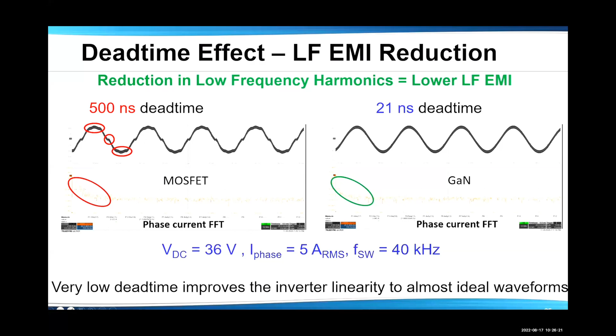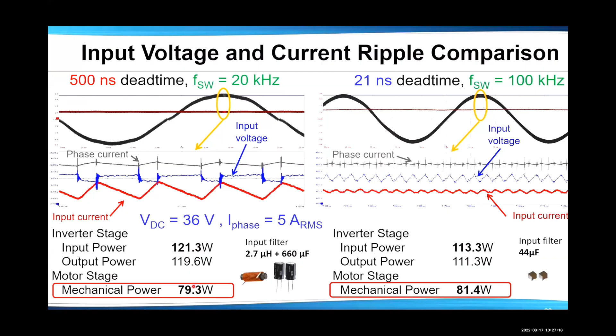Another really important thing is if you start going to higher frequency. This is an example from 20 kilohertz, 500 nanosecond dead time, same conditions, same motor. This is the input current from the battery. This is the input current at 100 kilohertz. This is the input voltage from the battery. This is the input voltage at 100 kilohertz. And here is the phase current. So all of this is to say that in this case there is the need to have a bigger capacitance, but here you can just live with a smaller ceramic capacitor. And an interesting thing is, mechanical power here looks to be slightly higher. Instead, here, given the same frequency and the same current, it's lower, but the input power is higher.